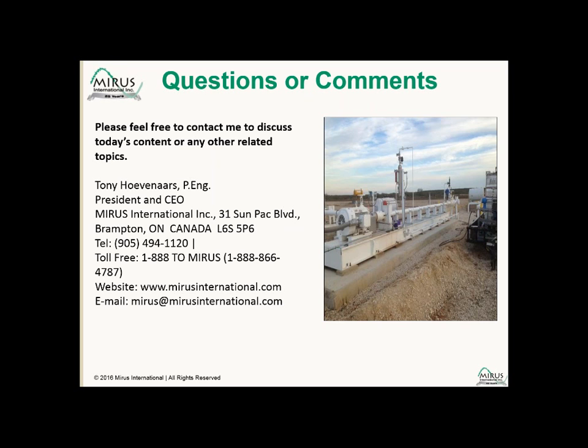Okay, so the first question is, is the month and a half payback a typical number, or was it only specific to this case? Good question. I would say it would be reasonably typical. Obviously, one application is going to be different from another, but you're dealing with the same level of harmonics typically. You've got a filter that's going to have the same level of efficiencies. It's going to reduce the harmonic content equivalently. So I think you could expect similar reductions, but even if it was slightly longer, it still produces excellent paybacks.